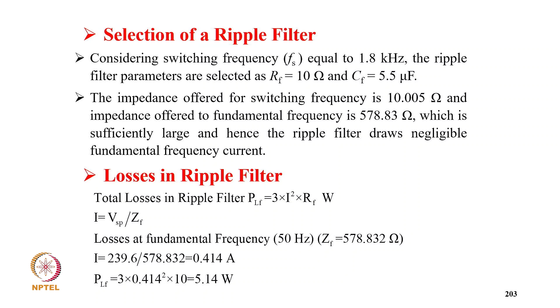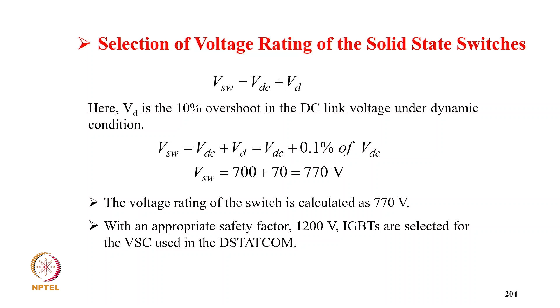And selection of voltage rating of the switch, so VSW equals VDC plus VD. VD is 10% overshoot, so putting a value, VSW is VDC plus VD, and it comes to 770 volt. So the voltage rating of the switch is calculated to be 770 volt. So with the appropriate safety factor, 1200 volt IGBTs are selected for the VSC used in the DSTATCOM.